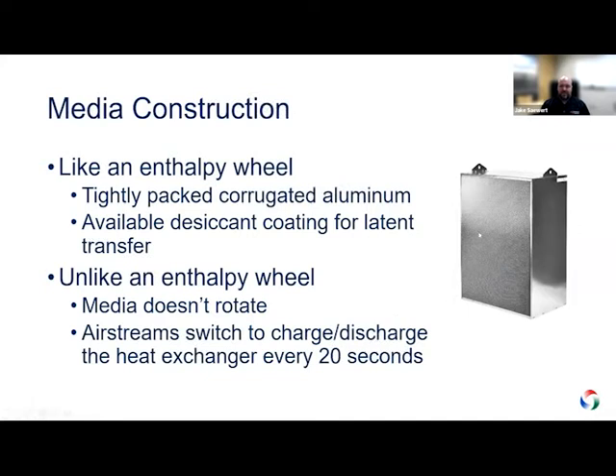The media of the heat exchanger, we're going to get into some more of the specifics of this, but the media is very similar to what you'd see if you went up to an enthalpy wheel and looked at that. It's tightly packed aluminum corrugate that is either mill finished, or you can get it with a desiccant coating on it as well for latent transfer in summer. Alone by itself, the aluminum media will actually transfer latent energy in winter. We'll talk a little bit about that as we get deeper into the presentation.